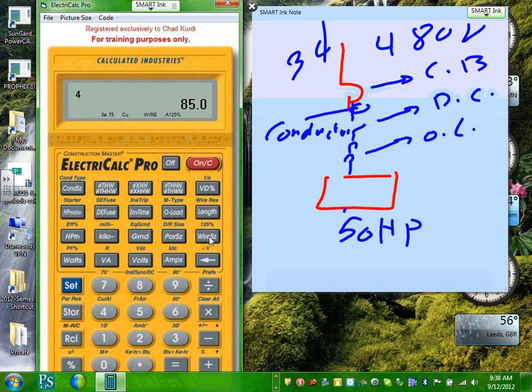Now, if you hit the wire again, it will give you 85 amps. It's good for 85 amps. Here's the circular mil. Here's the table. And it takes you back to copper. Where it says the 85 amps and it says a 4, does that mean you need 4 conductors?